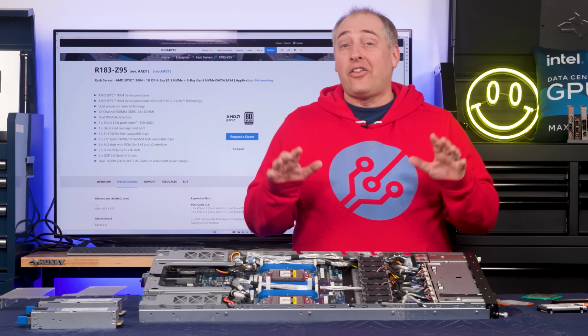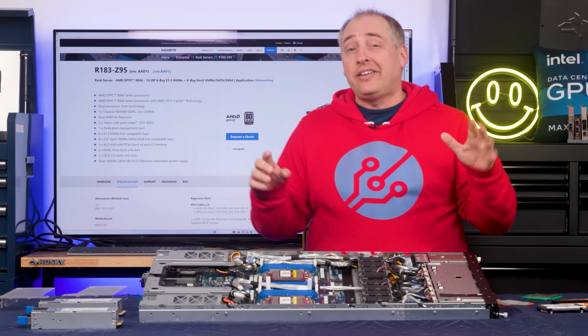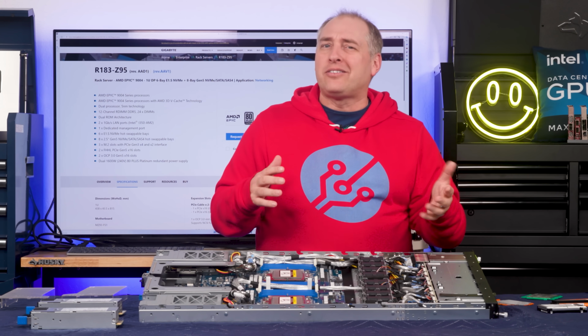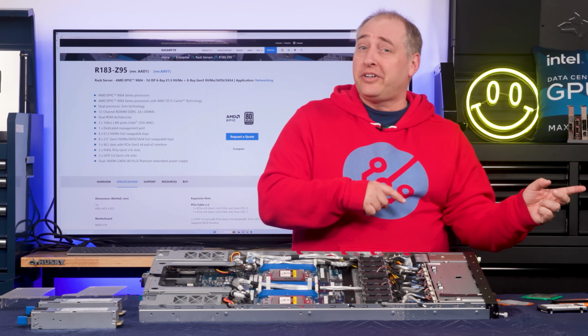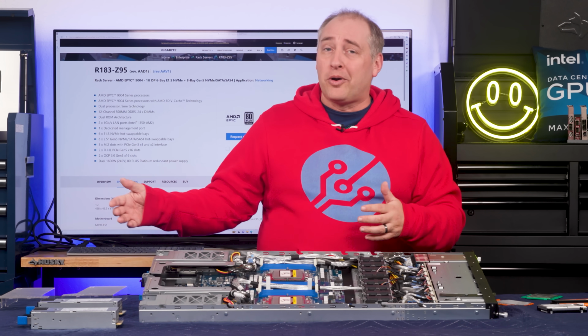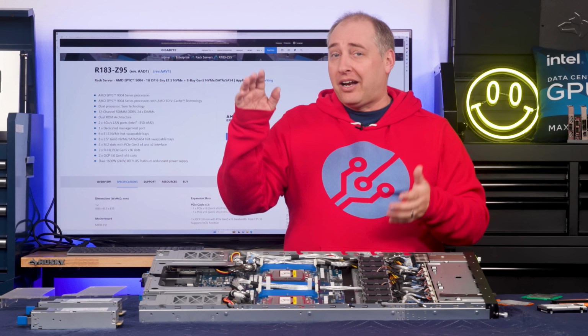Now, the data centers that we used to actually test these things in tend to run at 24 degrees Celsius, plus or minus about half a degree. Some folks run cooler data centers. A lot of folks now are running a little bit warmer because you get a little bit more efficiency by not having to cool it as much.